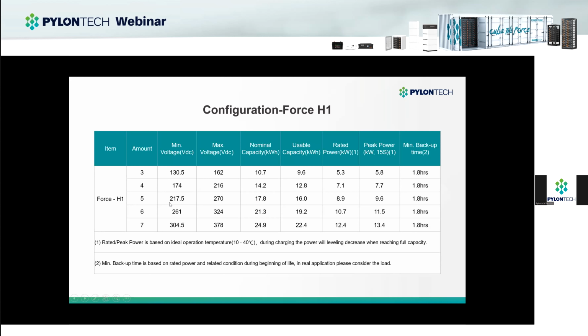As we know, every inverter has a different DC voltage range. So you need to make sure the battery's minimum voltage and maximum voltage are within the range of the inverter's DC side.